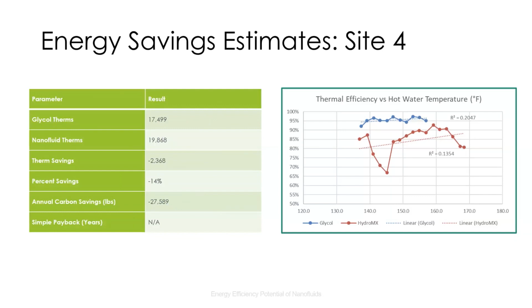We didn't attempt to normalize the operation of this system to a typical weather year because the loads served by this boiler were not those of a typical space heating boiler. We do feel that we received some reasonable data quality and had to make limited assumptions. However, there were some changes in apparent operating sequences that make us less confident in the results for multiple reasons.